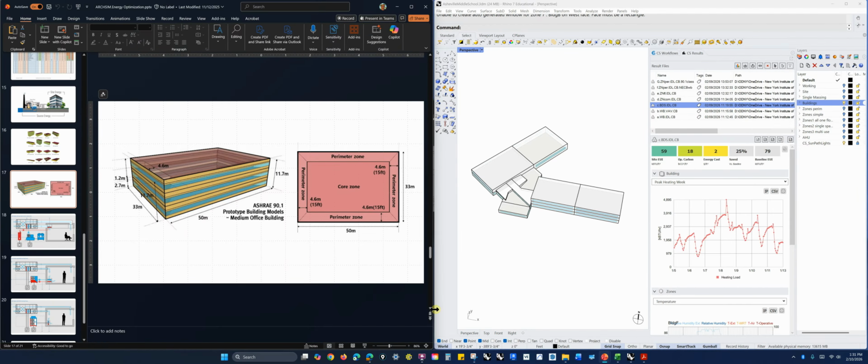So you definitely would have a south-facing, a north-facing, and an east and west-facing zone. If you're already heating and cooling, in the winter in a cold climate it's going to be a lot warmer on the south than on the north, so you can have different heating and cooling requirements. That's a different zone, right?